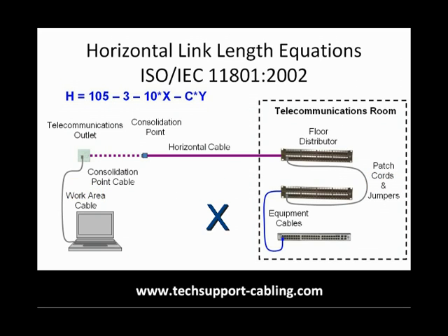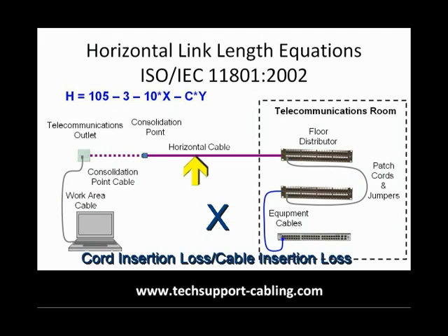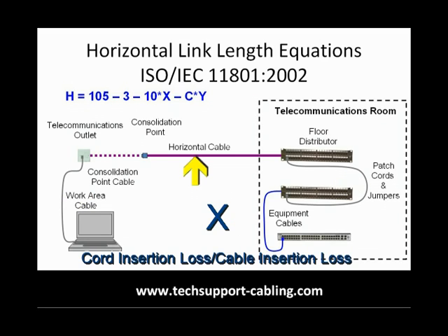X is the ratio of the cord or cable insertion loss to the fixed horizontal cable insertion loss. Supposing this is standard UTP cabling, the insertion loss for these cables may be anything up to 50% higher than that of the horizontal cable. In this case, X will equal 1.5.